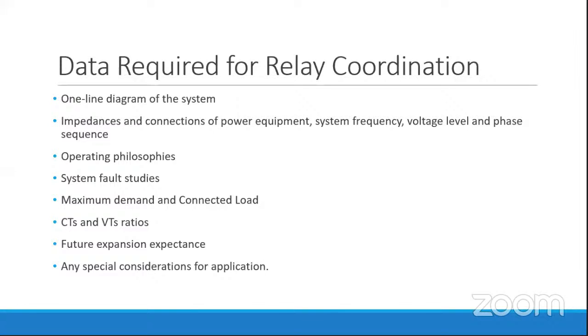The impedance of all the equipment is also required in order to calculate the short circuit or fault current, how they are being connected to the network, what the voltage levels are, and what the phase sequence is. All this data is required. What are the operating philosophies? If there are two or three lines coming to the network, or any in-house generators generating power for this network.